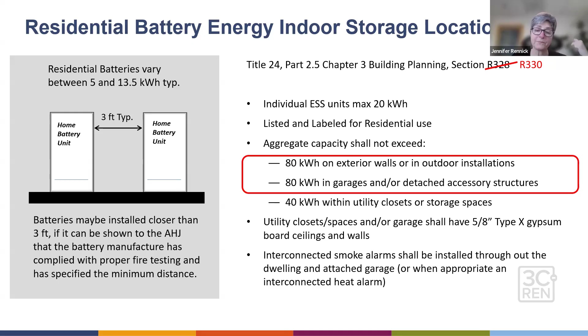If it's on the outside of a wall constructed with non-combustible surfaces, or outdoors on the ground and 3 feet away from property lines, that's going to be different than if it's on the ground outdoors and 10 feet away from property lines, for example. With each of these nuanced location requirements, you can have more and more batteries put together to meet your maximum battery size.